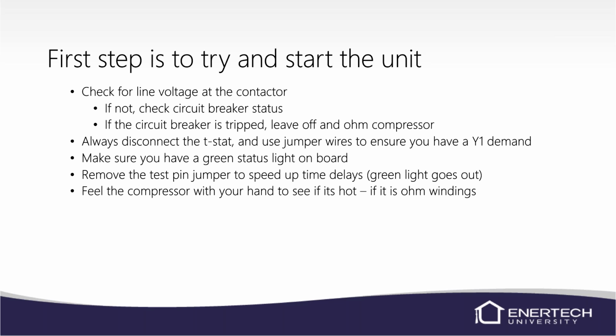If the circuit breaker is tripped, leave it off and ohm out the compressor. We'll cover some ohms of the compressor here in just a minute as well. You can disconnect the thermostat. We do have that removable terminal strip on the unit, so you can remove that and use jumper wires, or you can go to the thermostat. It's not that big of a deal, but we want to make sure there's a call to the unit at Y1. So make sure there's a Y1 call and make sure you have a green status light on the board, unless it's in test mode. If you pulled the test jumper on that lockout board, or some of the boards have a dip switch, if you flip that out, that status light will go out, so you won't have it.